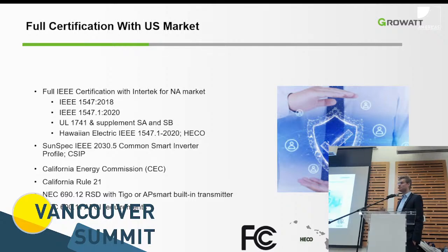No utility company uses that profile yet. It's pretty much a communication profile where the utility company can implement some bidirectional communication with the inverter to allow for higher penetration of solar in the grid. Now we are at probably single-digit percentage for most jurisdictions, but once more people have solar, it becomes more challenging for the grid, to have a stable grid and to provide fault ride-through situations and information for the utility company on what is happening on that low distribution segment. And that interface is there to implement future grid management features.